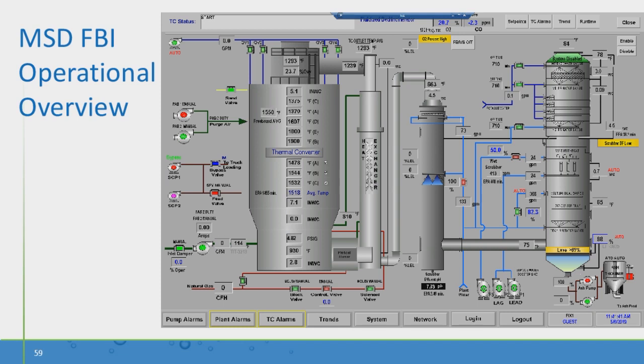And we can monitor all the temperatures throughout, as well as our scrubber differential pressures, which you will see flashing there as scrubber differential pressure low. At this time, that was because we were not providing air or gas or sludge into the incinerator, so that's not an accurate reading. But as it continues to rise up, you can see closer to the ambient temperature as we leave the stack, around 80 degrees. So to go all the way from 1500 to 80 is pretty impressive. I think that's good for this slide.